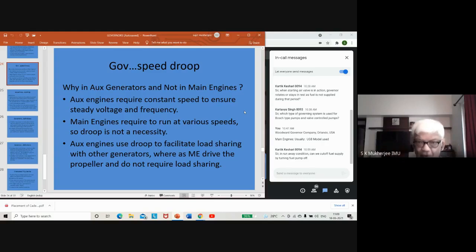So the speed droop settings of all the generators will have to be made more or less equal. Now, with the same setting, it does not mean that the generators will have the same speed droop. This is one big factor you will come to only through experience. Why? Because the inertia of the components of each of those items is a little different. So if I set this at 2%, on the other generator I have to set it at 2.5%.